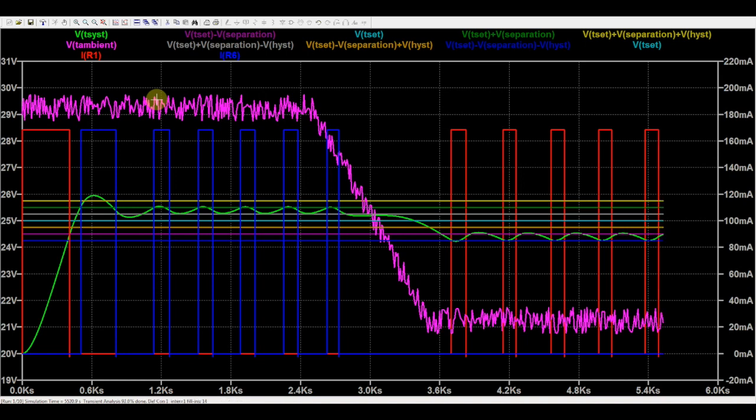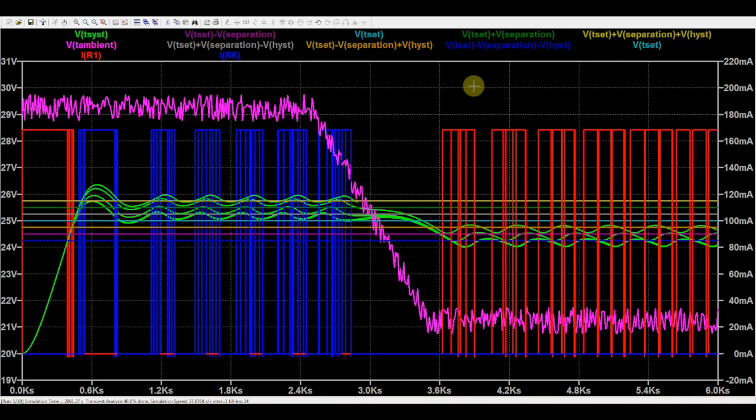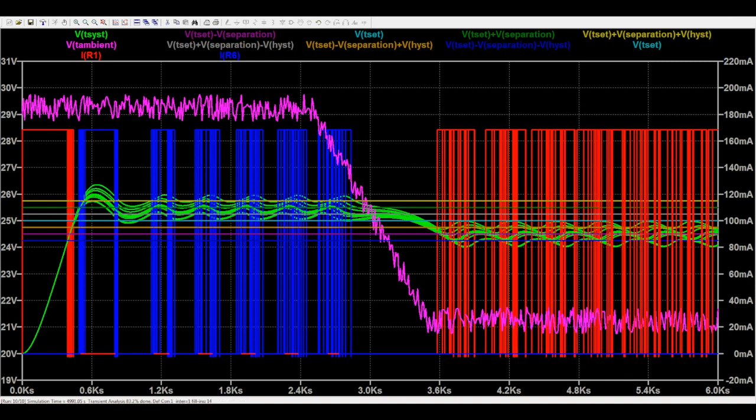As explained earlier, several simulations are done in a Monte Carlo analysis and after 10 runs, we see that cooling will be performed globally between 25 and 26 degrees C and the heating between 24 and 25 degrees C. So we are able to compute the contribution of all passive element tolerances to the temperature control.